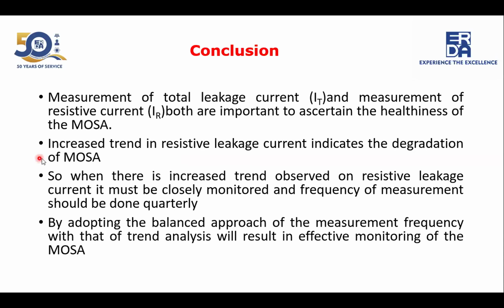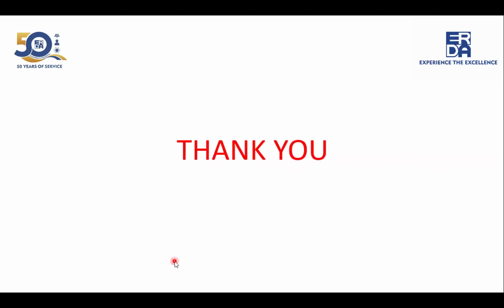For system reliability, we need to monitor the healthiness of the MOSA at equal time intervals, with frequency decided as 1 year or 6 months based on trend analysis. By adopting this balanced approach combining measurement frequency with trend analysis, we get effective monitoring of the MOSA. That concludes the two case studies of 132 kV and 220 kV surge arrestors, derived from trend analysis for condition monitoring of the surge arrestor.